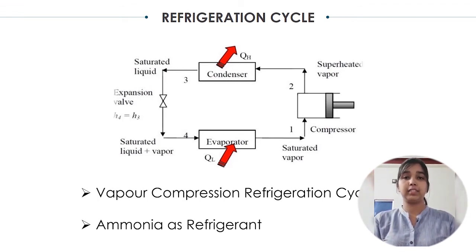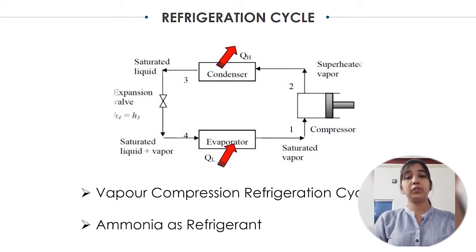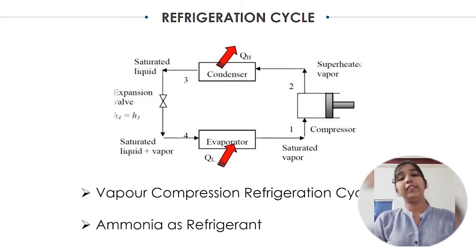the same process. Here we are using a two-stage compressor, as the staging of the compressor will result in a reduction in work done to compress the vapor, and it will also prevent mechanical problems, as a mechanical problem will be faced when a single stage compressor is used, because there the temperature of the refrigerant will be high. Now here we are using ammonia as the refrigerant.